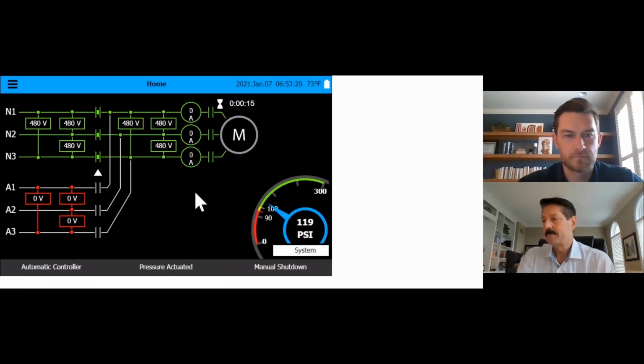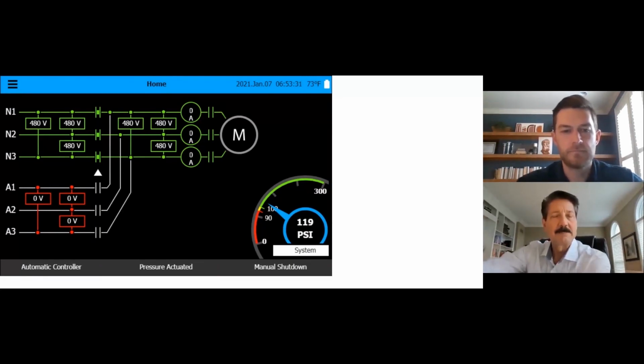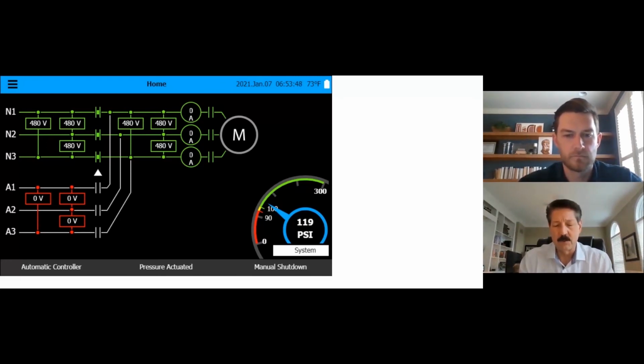I'm going to do a regular test of the generator. Now, again, when we do NFPA 25, typically by code, diesels should be tested once a week for 30 minutes. Electrics typically are once a month for 10. And depending on the type of location, the cities and so forth, and really the density, you might end up doing this weekly with electrics. But I'm going to do a test here and do a transfer switch test.